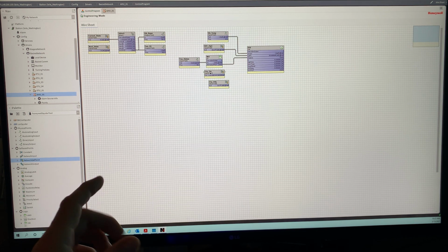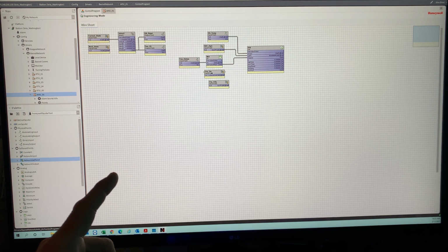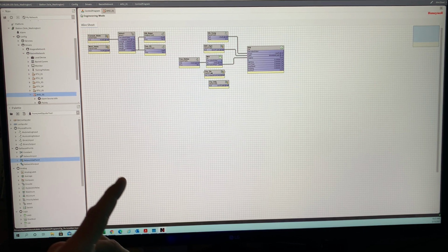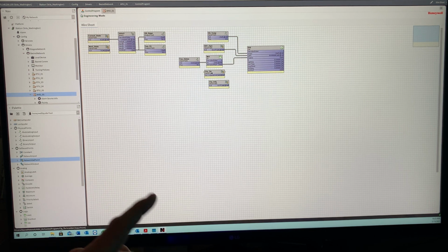Usually with static pressure transducers, things like that, we'll start off with a 10 and we'll modify it as we go. Also, another reason we make this a set point is that it makes commissioning easier, so you can make your adjustments. If you made this a network input, you wouldn't be able to make the changes as easily as you would in your configure. So then our set points, my bad, I'm sorry.